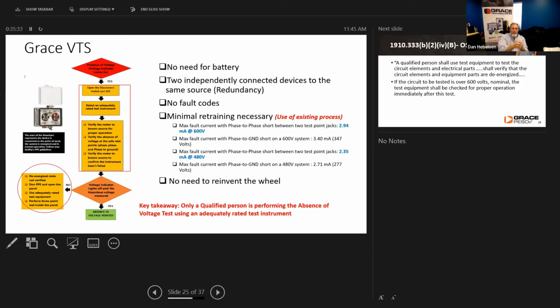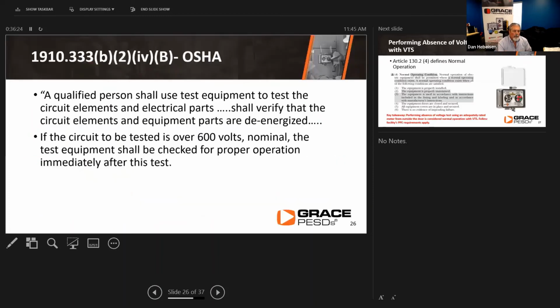Basically, we get the opportunity to retrain how people are going to do this, use their existing process for a lockout tagout procedure, but we're going to create an environment where it is not exposing them to that hazardous energy. So when you talk about approaching the cabinet, you're going to verify, is it in normal operating conditions? Then you're going to verify, is there voltage here, yes or no? And then you go through your procedure. We don't want to reinvent the wheel or have to retrain. What we have done is taken the risk control hierarchy, taken the best practices of elimination of risk or substitution of risk through engineering controls, and created an environment where they can do that lockout tagout procedure in a safe environment without exposure.